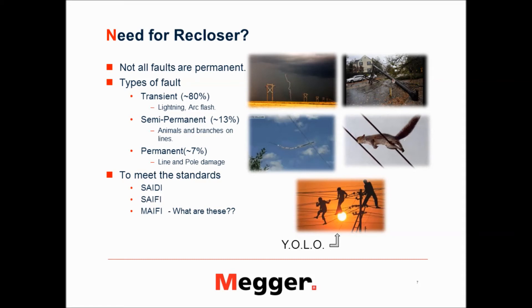Only about 7% of faults are permanent, caused by storms or similar events. The final one is a special kind of fault — I want to call that a 'YOLO fault,' meaning you only live once. Those kinds of faults are permanent and you need to clear those faults before you restore your system. That is one of the main reasons why you need a recloser — in case the fault is not permanent, you want to restore the system and the generators, and restore the stability of the grid again.